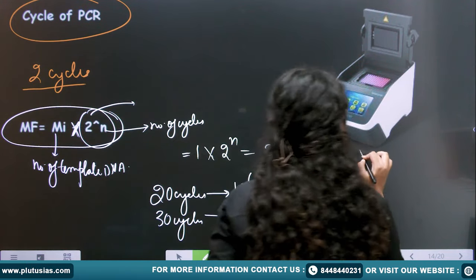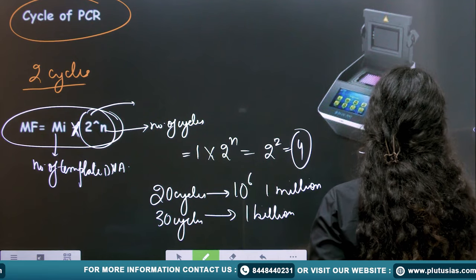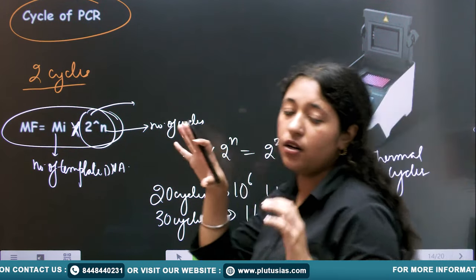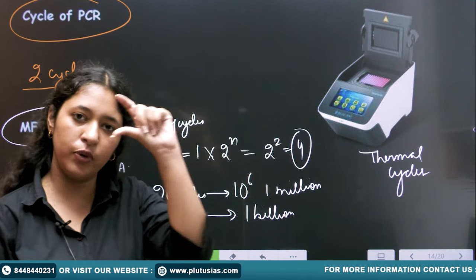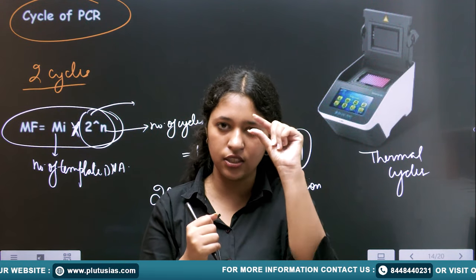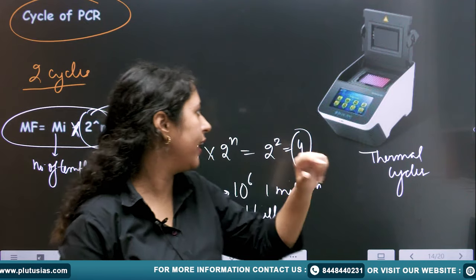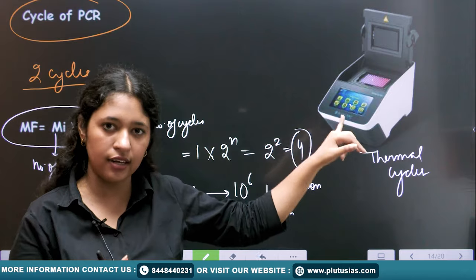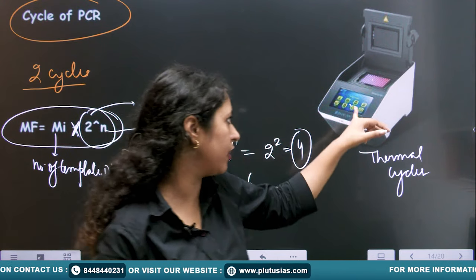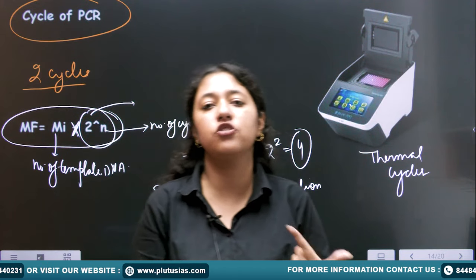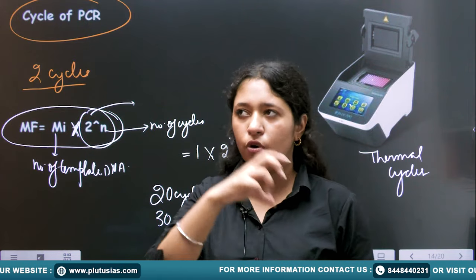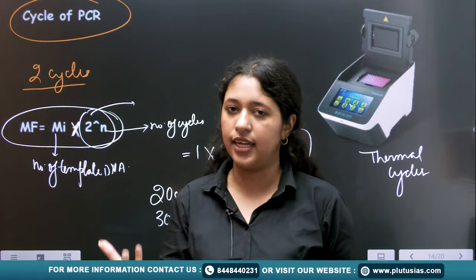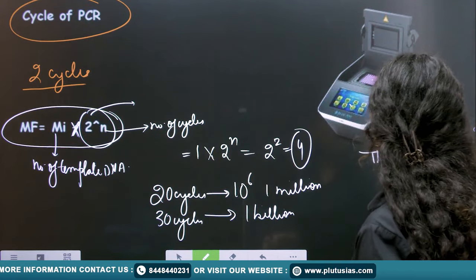The thermal cycler is the instrument in which PCR is performed. We put all the components in small microtubes, place the tubes in the machine, and set the temperature, number of cycles, and amount of DNA. The temperature is run for 3–4 hours according to the product and timing decided.